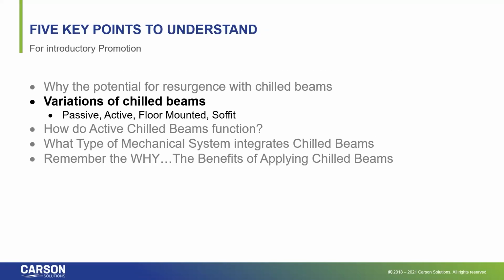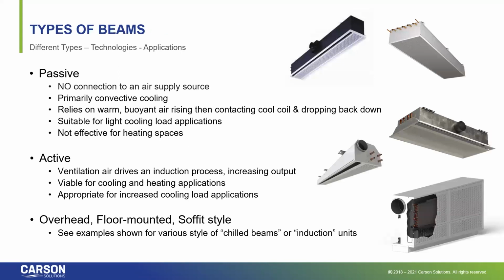There are two predominant variations of chill beams. One is a passive beam, and as its name implies, it is passive. It doesn't have an outside air source delivered to it. It acts as a radiant cooling device. It relies on the warm, buoyant air moving upward until it comes in contact with the cooled surface. Once that air becomes cooled, it drops down due to the buoyancy relationship within the space. It's suitable for light cooling load spaces, and it's not a viable option for heating within those spaces.